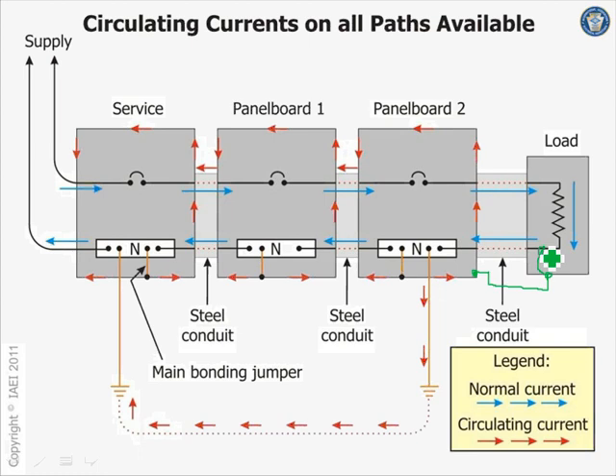Would the equipment malfunction then? We actually use isolated ground outlets inside the rack, and we use plastic sleeves on all the metal conduits and actually isolate the rack from the cement with the pad. Otherwise, we get that problem all the time, where you get voltage on the coax or voltage on the Ethernet cable. Yeah, no, I hear you.